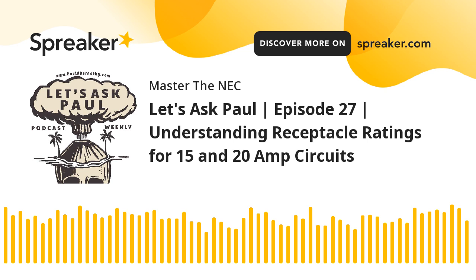All right, now, what I'm going to do is answer the gentleman's question. I assume it's a gentleman. I'm going to really logically go down the list by talking about 15 amp breakers and 20 amp breakers and how they correlate with a receptacle, because that's what the question is, the ratings. Okay, so we'll start with the duplex receptacles and we'll end with simplex or single receptacles. And you're going to see that the code is slightly different. It tells you can do one thing for a simplex, but you can't do this for a duplex. And I'm going to explain it, so don't worry. And I'm going to do one at a time, make it very simple to understand.